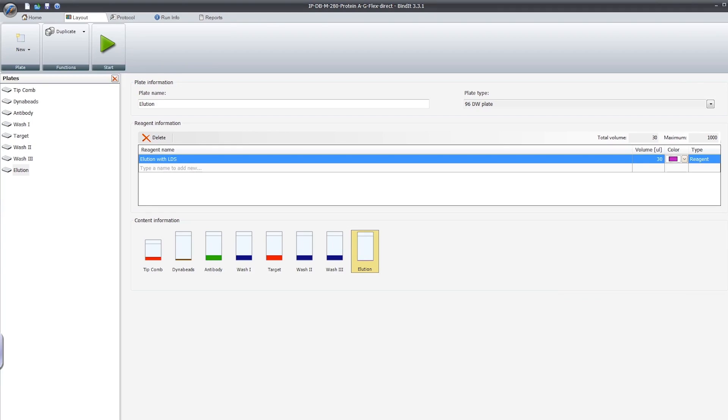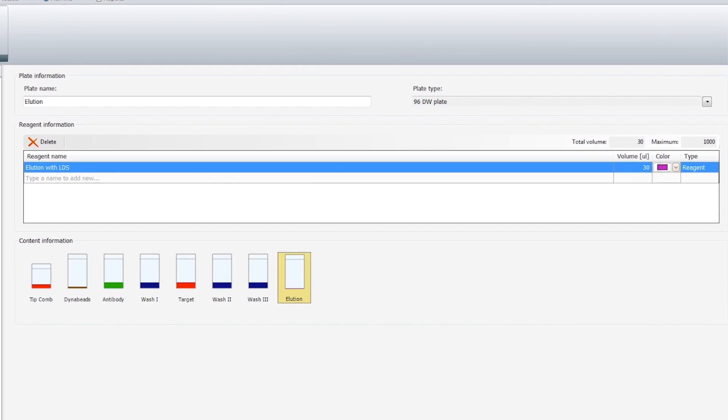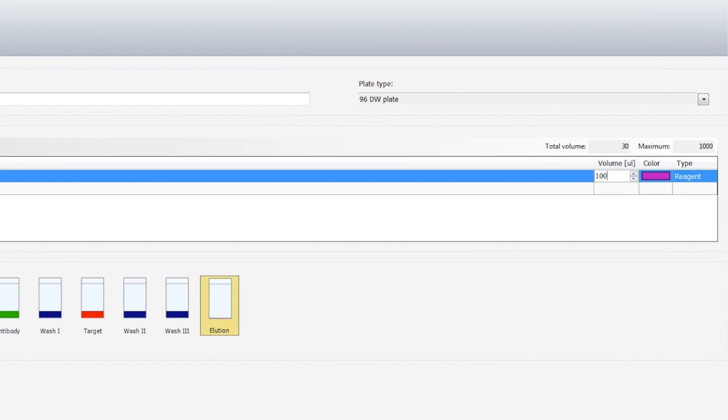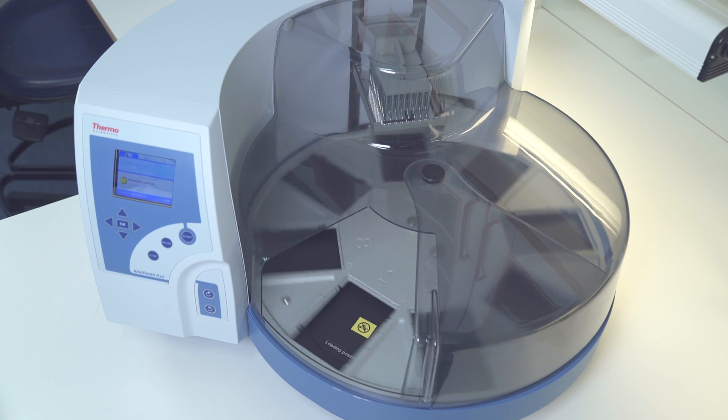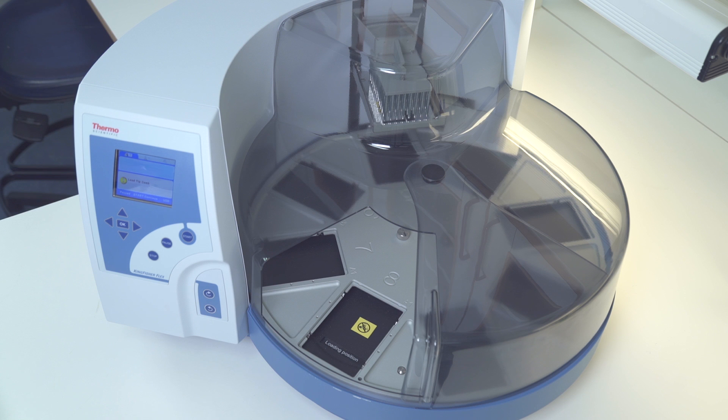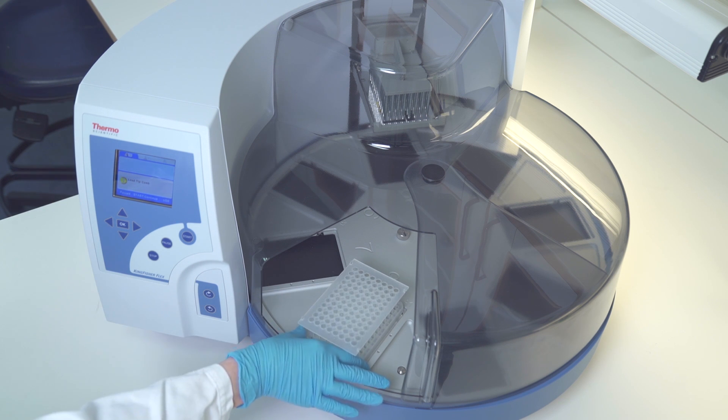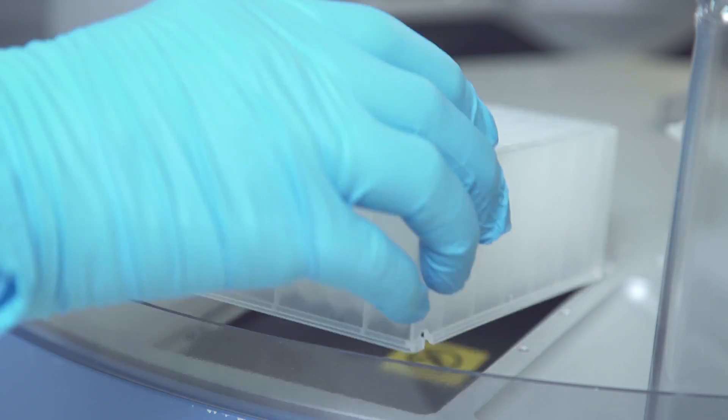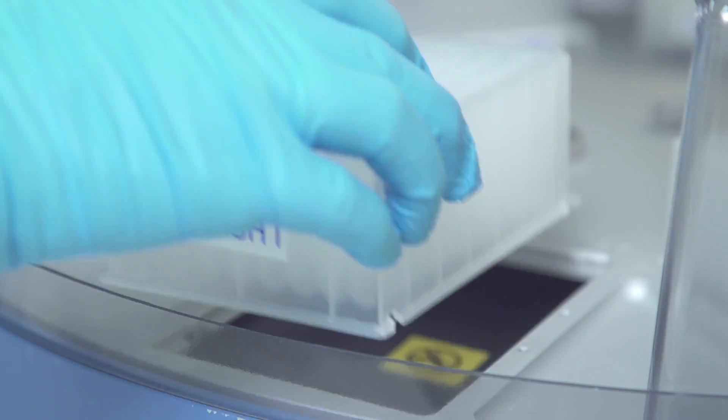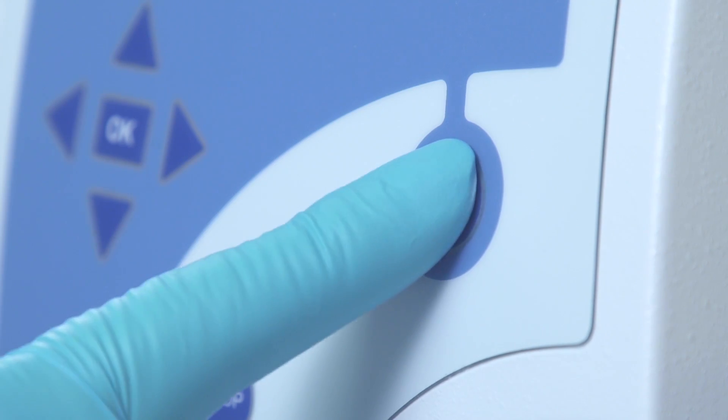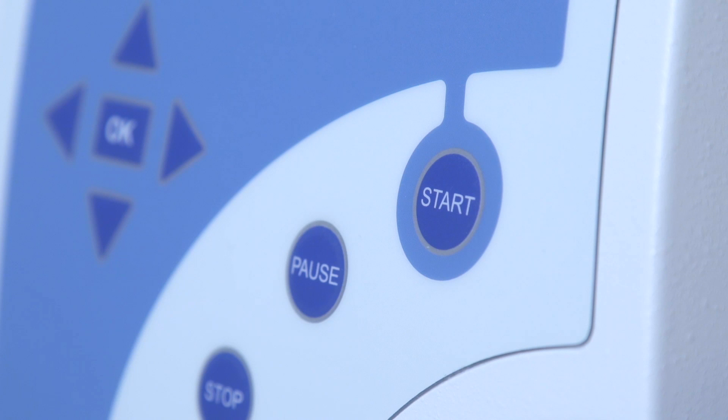You can use the standard 40-minute protocol as is or easily modify it and save your own custom versions with the user-friendly BIND-IT software. Loading the plates is easy and Kingfisher will tell you which plate to load into each position. Load the tip combs and the seven plates in sequence. When all plates are loaded, press START to initiate the IP protocol.